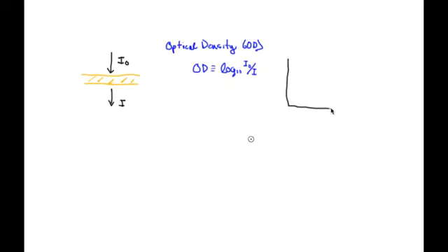If I plot optical density versus dose, there's a very important curve here. Number one, it's not linear. It doesn't follow a line. It has a special shape. So it might start here at 0.2. That might be a typical value. If you have zero dose, there's some baseline fog level, and then it comes up and it saturates.